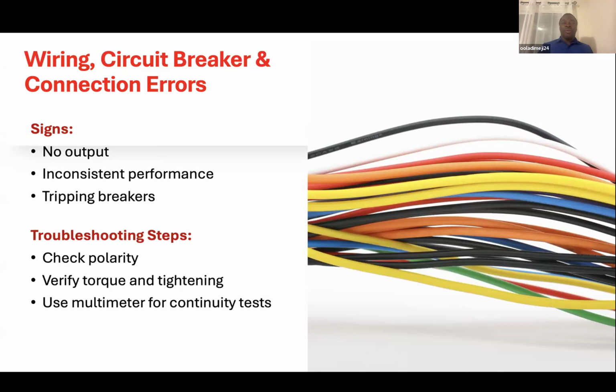If you are not getting any outputs, then is it that the cable is not good, maybe there is breakage within the cable? Then you know that okay, there is input to the cable. I can measure my current from the output of the inverter, but I'm not getting anything from the other end. Then you know the system is the problem. The wire which is traveling to it is the problem.